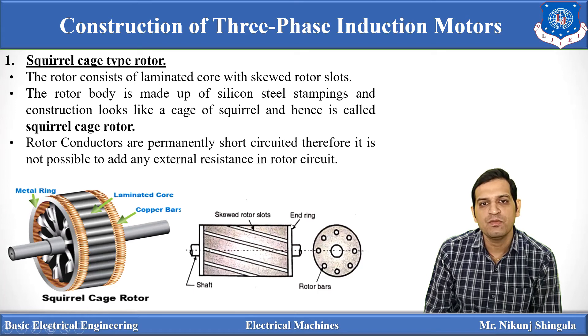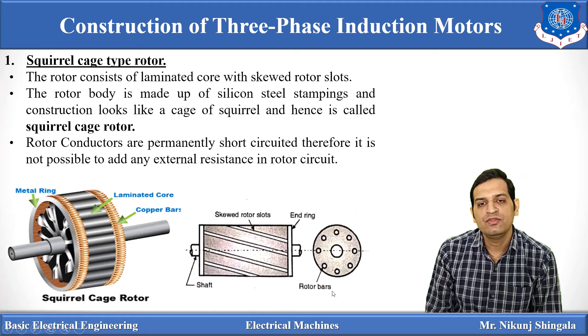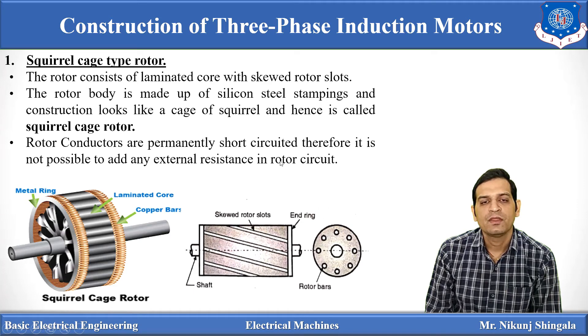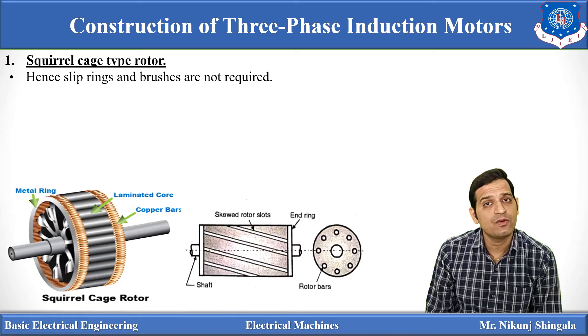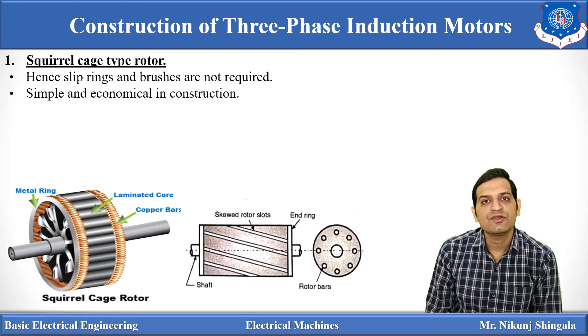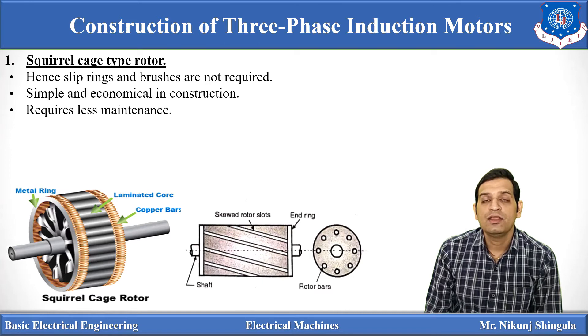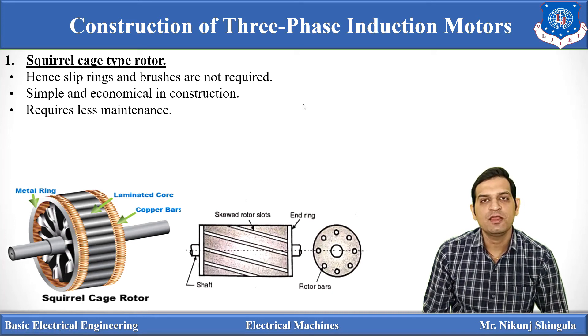This is a cut section of the squirrel cage rotor. You can see the skewed rotor slots, the rotor mounted on the shaft, and the copper bars short-circuited at both ends by end rings. Slip rings and brushes are not required for this kind of rotor because external resistance cannot be added and both ends are short-circuited. The construction is very simple and economical. It requires less maintenance and is long-lasting. This type of rotor is used in lathe machines and drilling machines.